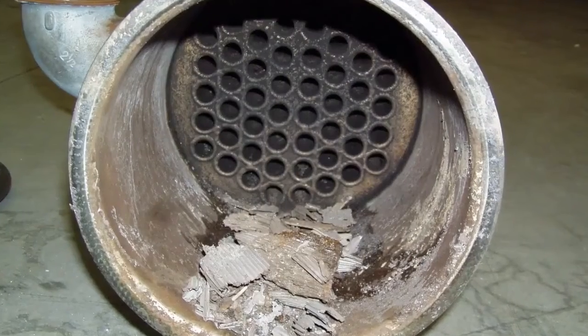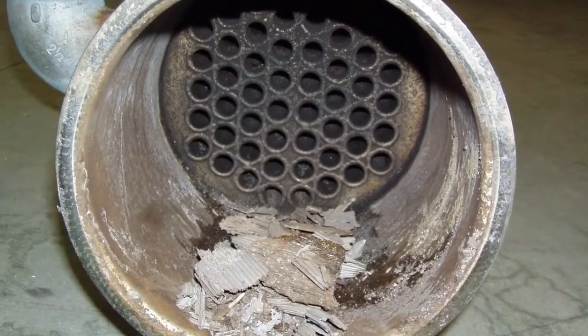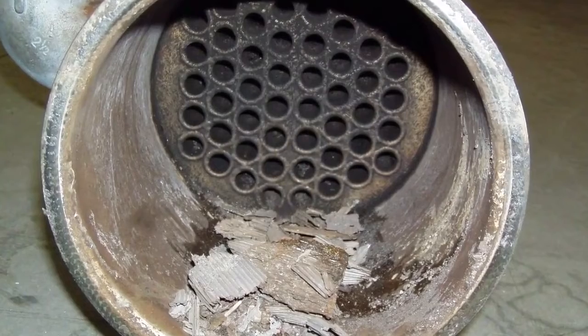Now, I don't want to go into the details of the design, which may require more detailed explanations. Simply put, by looking at the shape, it is intuitive that I can disassemble the two heads of the exchanger, enter with a brush, and clean the tubes tube by tube, and remove any dirt that accumulates. On the outside, in the mantle, a typical heat exchanger is welded. The tube bundle can't be removed, so I allow the clean fluid to flow through the mantle.